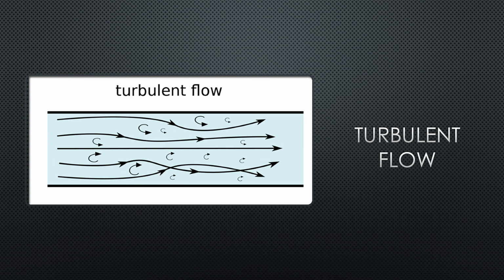When a fluid's velocity is increased, turbulence can be introduced, which disrupts laminar flow. This is called turbulent flow. Unlike laminar flow, turbulent flow has many irregularities. The fluid molecules often move in a random, chaotic manner, mixing the layers of fluid. This erratic movement requires more energy than laminar flow to move the same distance, and this wasted energy makes turbulent flow highly inefficient and extremely undesirable within a hydraulic system, even if it moves faster.